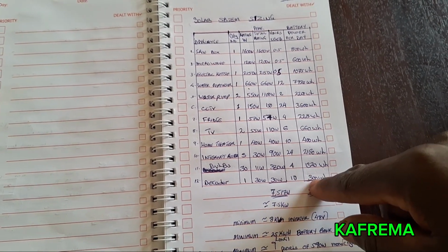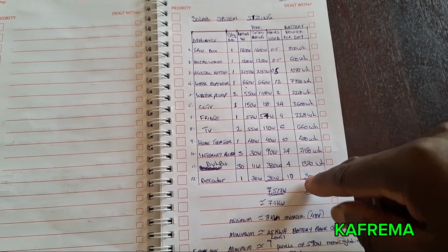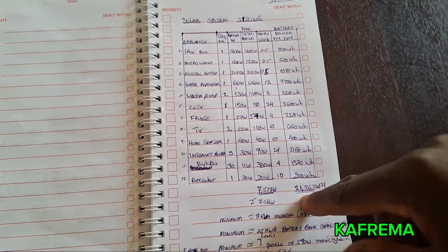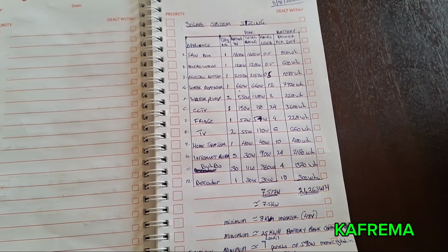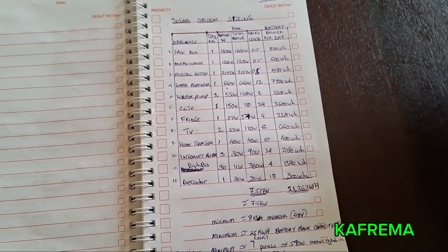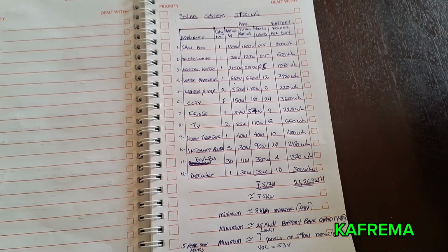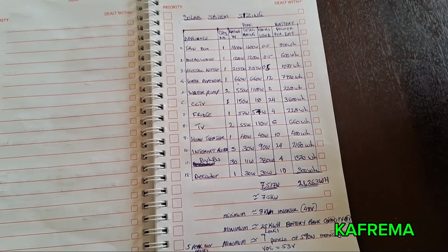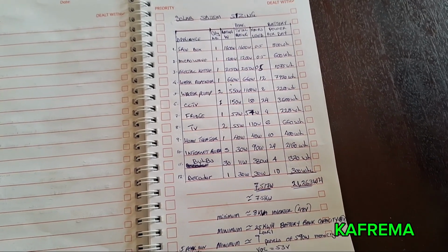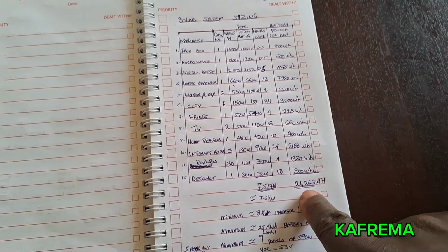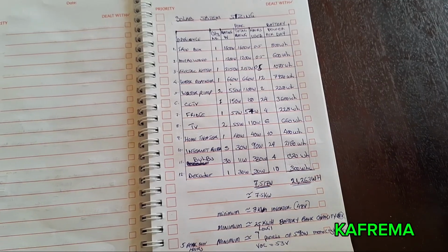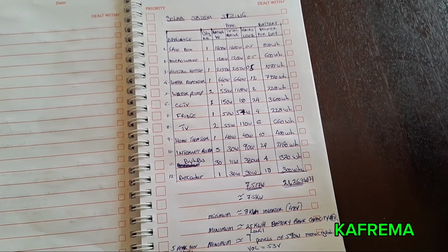This is the power required to use in a whole day. And if there is no sun for one day, this is what we will use. We call them autonomous days. If there is rain, according to your area weather, how many days can you stay without intense sun to charge your battery? We are going to take this power for one day times the autonomous days. How many days can your battery bank support you and all your equipment?